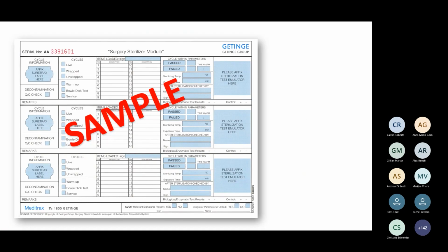So when you're looking at your recording stuff, you're going to pick that it's a live cycle, that you've got wrapped or unwrapped instruments in the load. If it's a test cycle, a Bowie Dick test, or during service when the technician's there, then you can tick those as well if they relate. Then you put your load in. So you might have incision kits by 3, you might have forceps by 4, whatever.